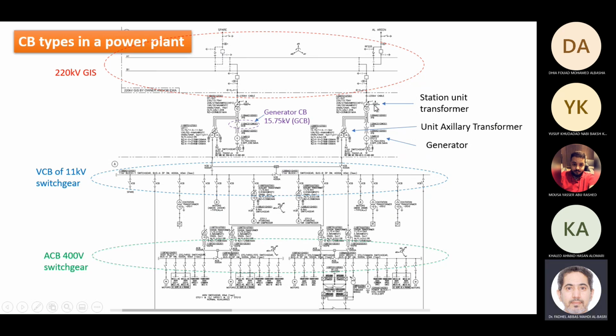The star is grounded to limit the fault current, and then we have a breaker that connects either to this bus or this bus. Between these two you see a small line. These are the isolators, or disconnectors. And this is a breaker, and here you have a small disconnector connected to earth. Suppose I want to take the breaker out of service: you switch it off, open these two isolators, and ground its terminals through these small disconnectors.